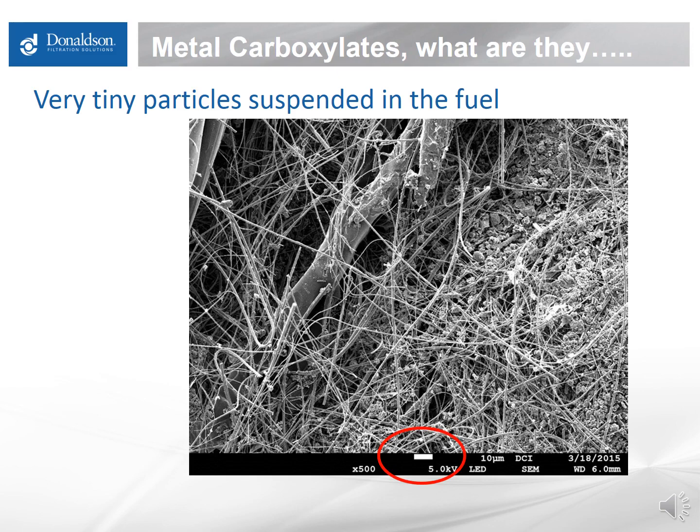The scale bar in this image is 10 microns, illustrating that this material is substantially made of very fine particulate. The larger particles pointed out by the arrows are nowhere near that 10 micron scale bar — they're perhaps 5 to 6 microns in size. Most of the other small particles are well below 5 microns and just pass right along until they hit a high-efficiency filter.